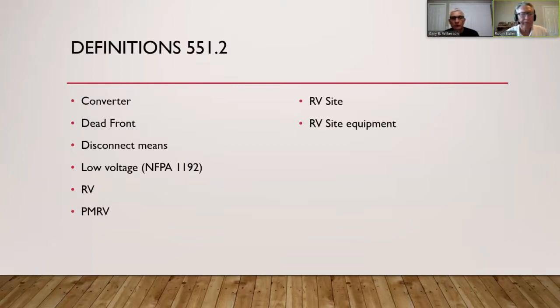Okay. So there's 2 covers to be removed, the outer cover and then the inner cover. And when you remove the inner cover, then you can actually get to the wires and the energized parts. That's when you should de-energize the equipment and open that cover, and then you could do work within the panel. Okay, good point. De-energize the equipment. Yes. In other words, don't be taking that second cover off if it's energized. The outer cover you can open up to reset a breaker or to turn it off or turn it on. But the inner cover, which is called the dead front, is the one that they want to separate you from the live parts, and you should never take that off until the equipment has been de-energized.